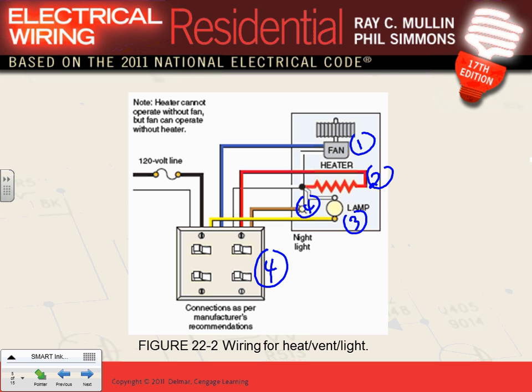So who cares? When you come over here, guys, overcurrent protection device 20 amps, and this conductor is going to be what? 12-2 NMD cable coming to this equipment, right? 12-2 based on the manufacturers. If you were to size this, which we typically don't size, the manufacturer will tell you provide a 20 amp dedicated circuit for this appliance. Done. That's a fan combo.